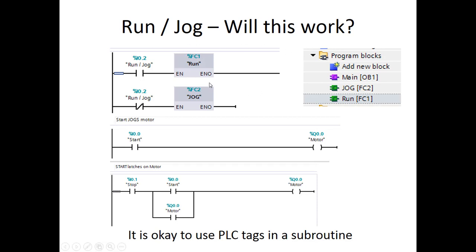Let's take a look at the first run-jog example — will this work? What we have here is that toggle switch. We're either going to be in run or jog because we're using it as a single input. So it's scheduled so that either this function is going to run or this function is going to run — both of them are not going to run at the same time. That's one way to schedule it.